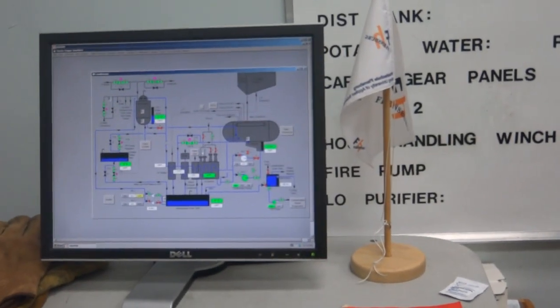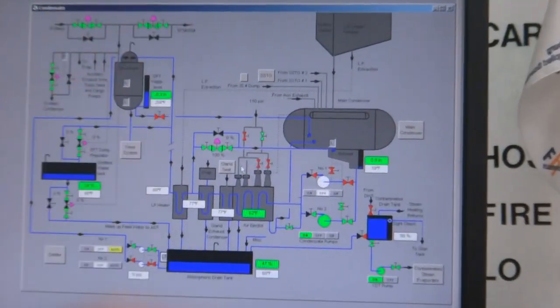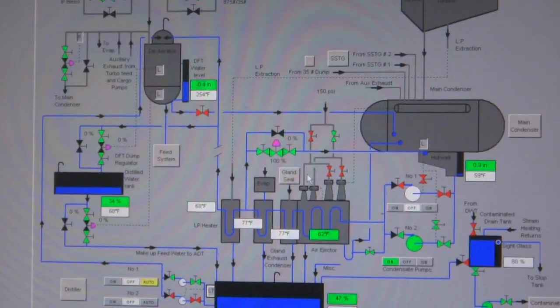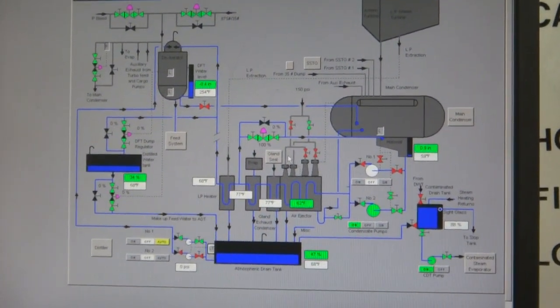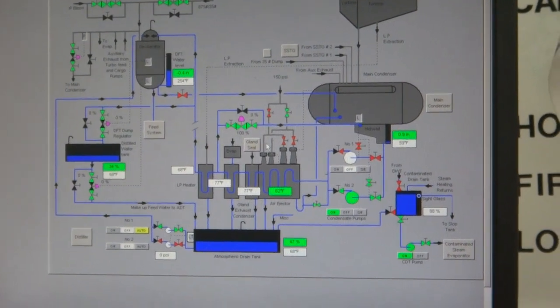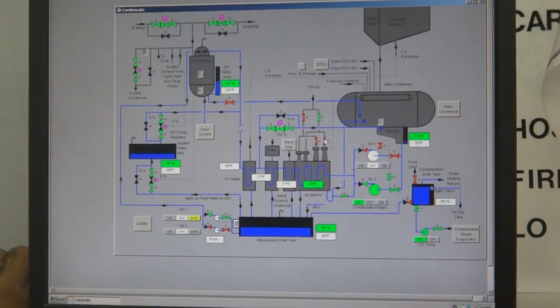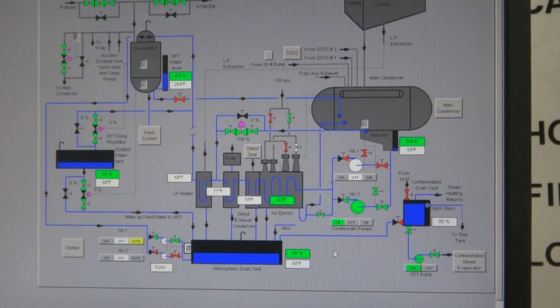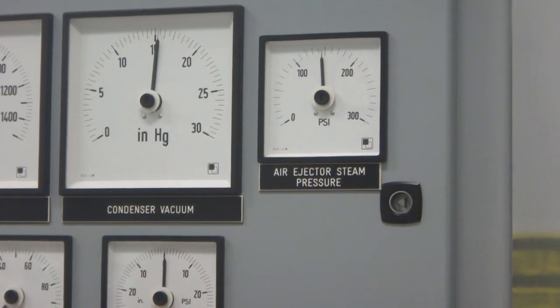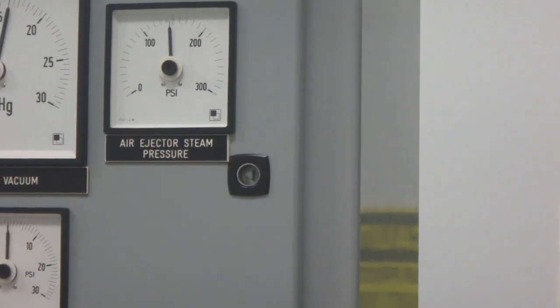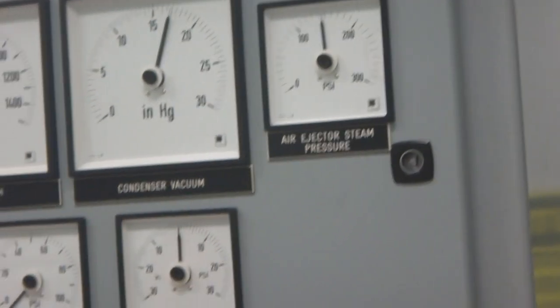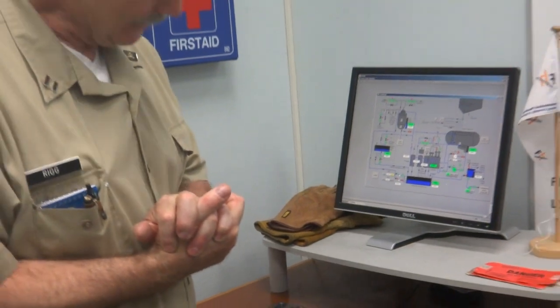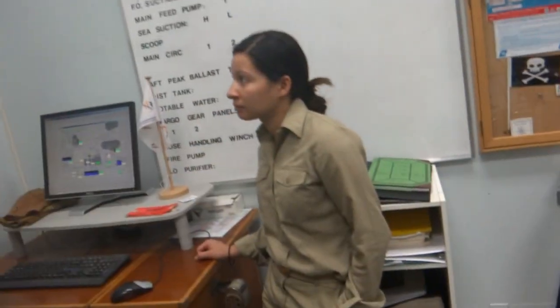And what'll happen, it's usually a little faster to warm up the turbine casing with just the after set on. Because that means it has less vacuum. It has a higher pressure. The saturation temperature at a higher pressure is greater. It heats it up quicker. Or we can go ahead, trace it out, make sure you get the right one. Putting all four on will make it worse. And now you'll see it coming up the rest of the way. As it approaches the final point, it'll start slowing down. This is 5 time constants. You guys have probably heard of that somewhere. And now that's it. That's how you get vacuum up. So now, guess what we're going to do? Do it again. So shut the condensate recircs. Go ahead, set up the 150.